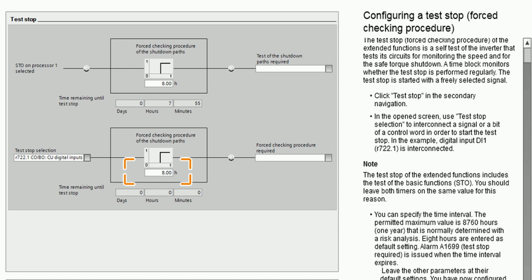You can specify the time interval. The permitted maximum value is 8,760 hours, 1 year. That is normally determined with a risk analysis. 8 hours are entered as default setting. Alarm A1699, test stop required, is issued when the time interval expires. Leave the other parameters at their default settings. You have now configured the test stop of the extended functions.